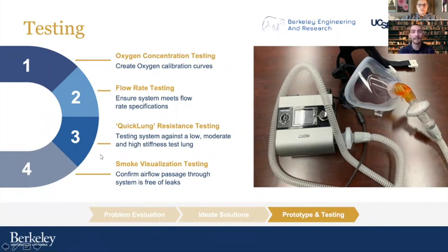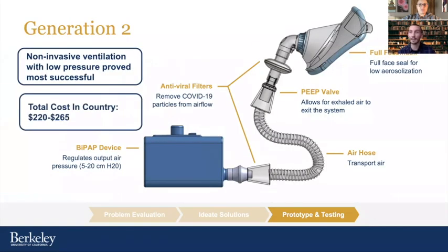And then I think the last thing that we tested was the smoke visualization testing to make sure that there were no leaks throughout the circuit of our system design, because we did not want any of the aerosolized COVID-19 particles exiting the system at a part of the circuit which it was not being filtered. So we used a small smoke gun, and then we could actually detect where any aerosolized leaks were occurring. But our system proved well, and it did not have any leaks. So from this point, we basically finalized our design of the ventilator system.